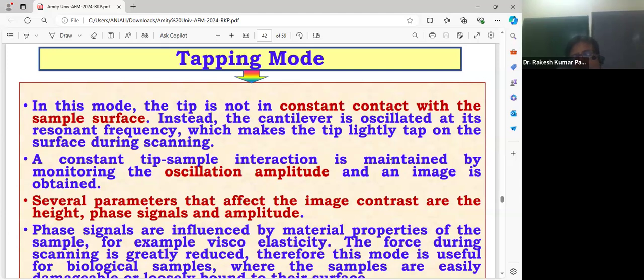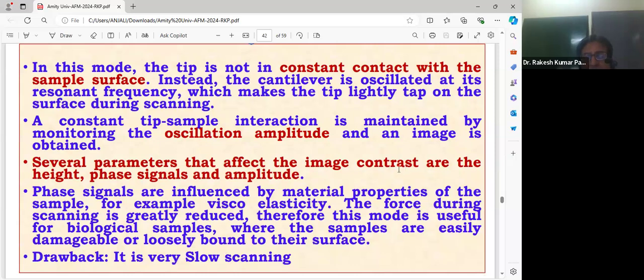We have seen contact mode and non-contact mode. In this tapping mode, it is neither contact mode nor non-contact mode. It is just oscillating, and with this oscillation, you can monitor the surface. A constant tip sample interaction is maintained by monitoring the oscillating amplitude and an image is obtained. Several parameters that affect the image contrast are the height, phase signal and amplitude. Phase signals are influenced by material properties of the samples.